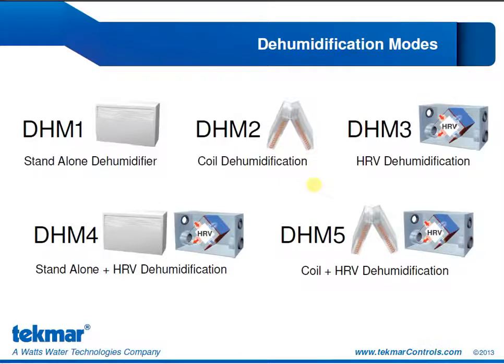There are 5 dehumidification modes. The first mode, mode 1, is for a standalone dehumidifier. An example of that would be a compressor-driven console unit. They have their own fan to pull air over 2 sets of refrigerant-filled coils to condense the water vapor out of the air.